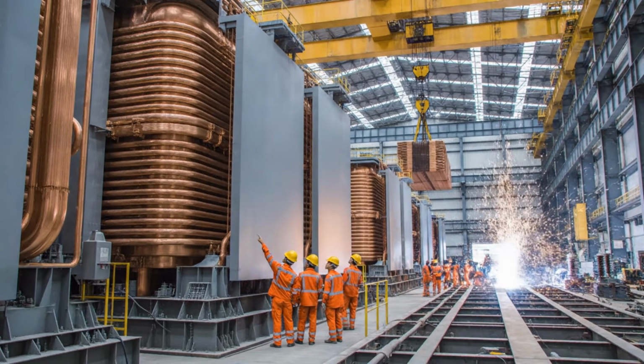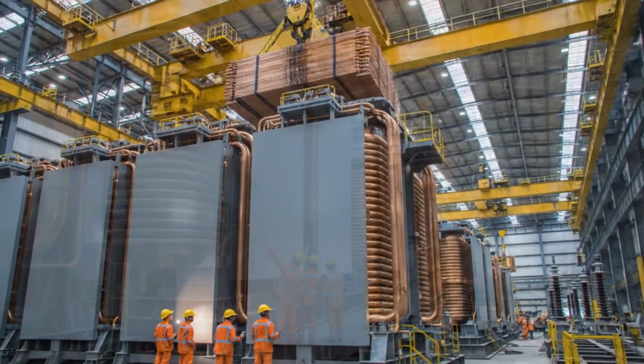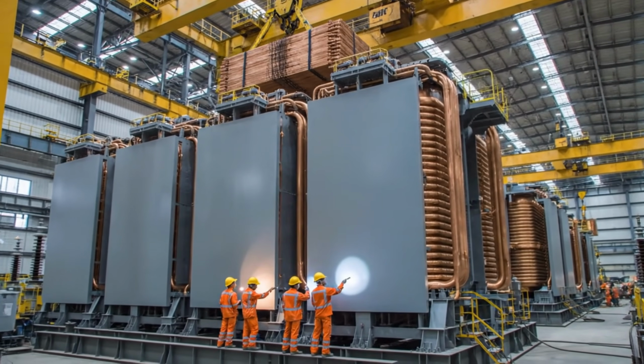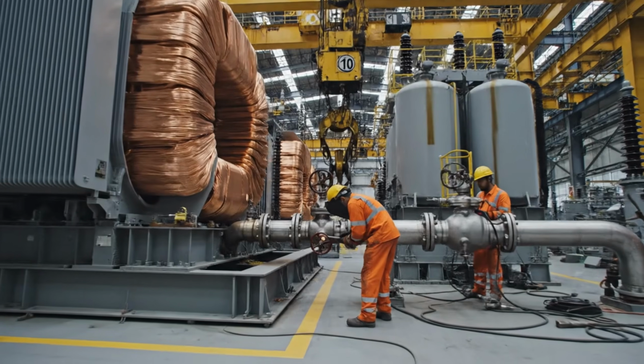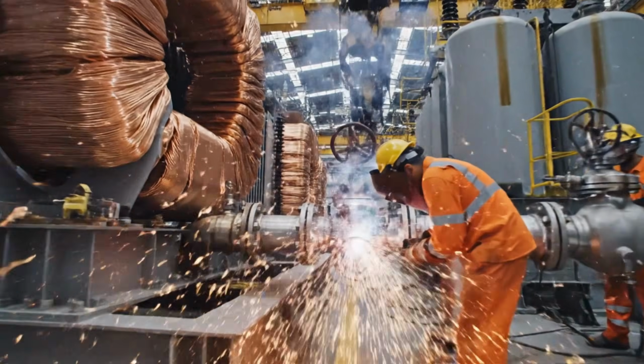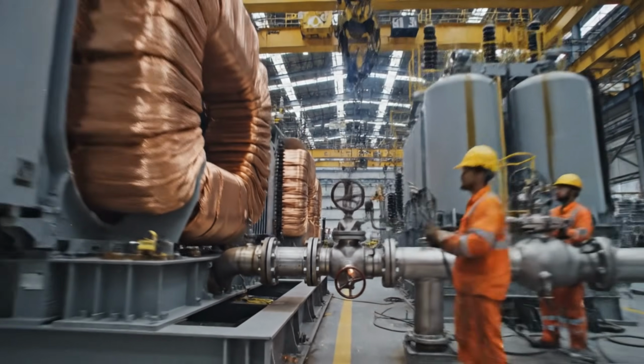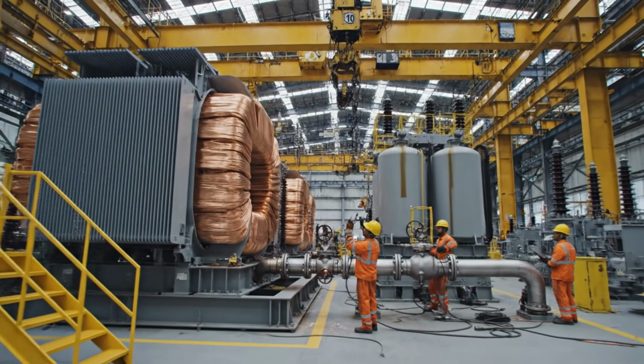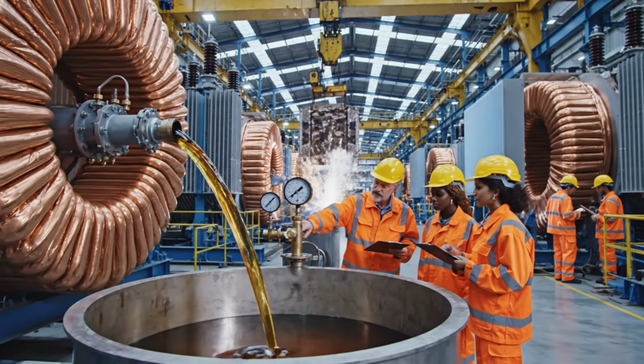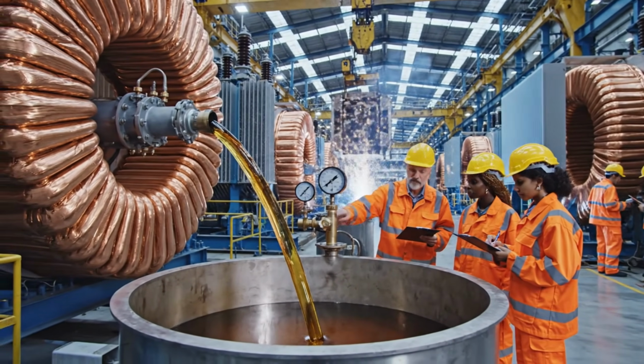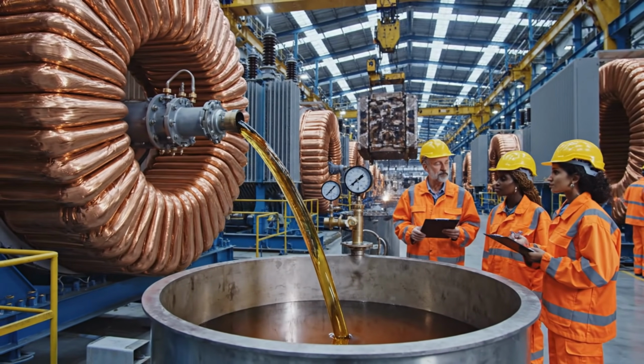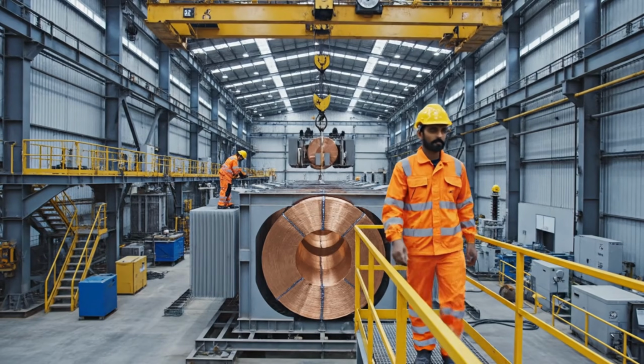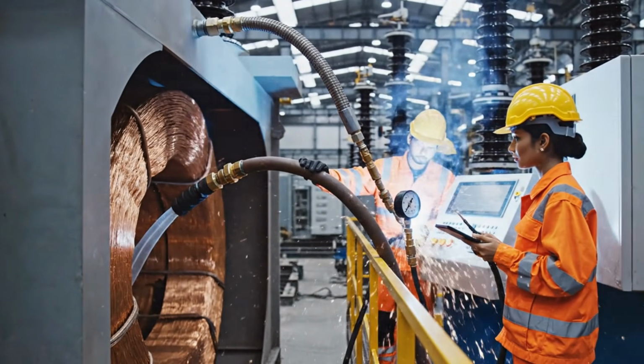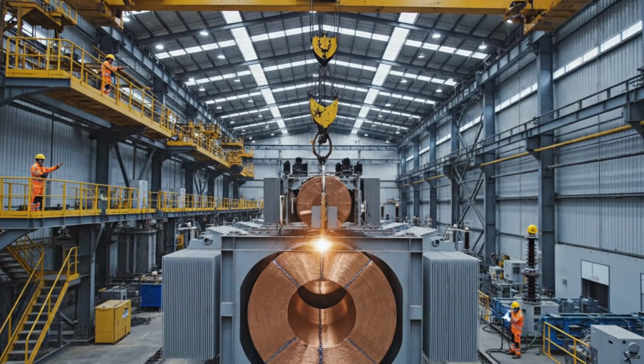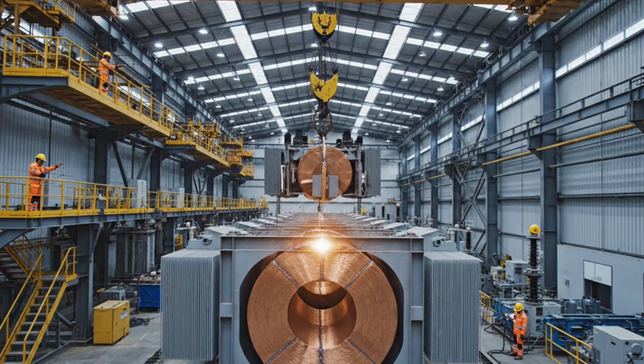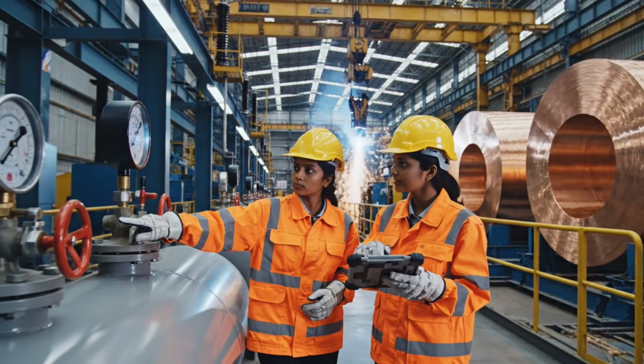Check the insulation levels on the high voltage winding. Looks good from here, but let's double check the connection points. Crane, lower it slowly now. Watch the alignment on cell 4. Pressure looks stable on the oil line. Oil levels look stable on the main tank.